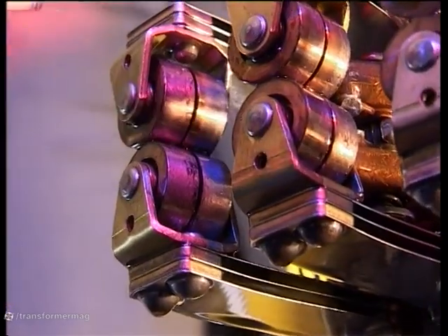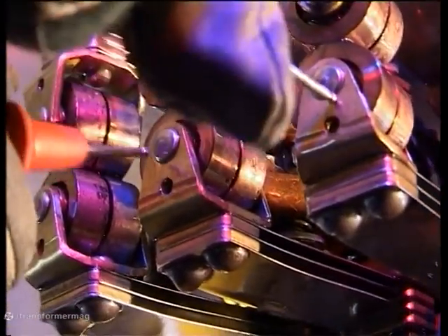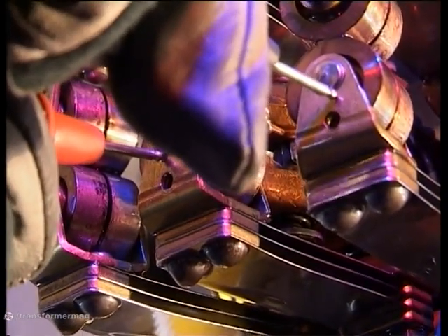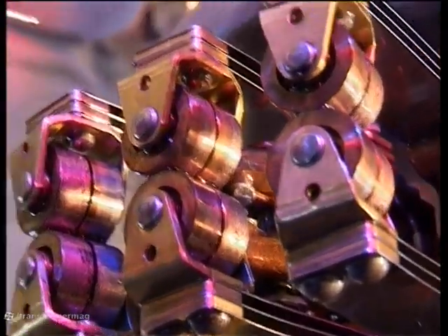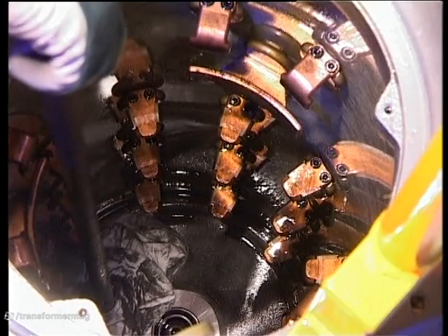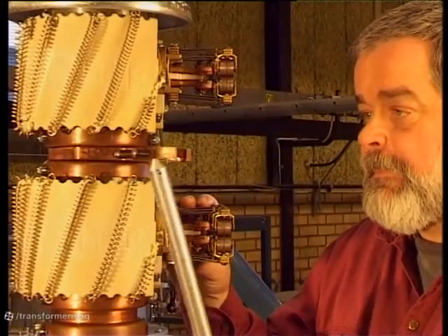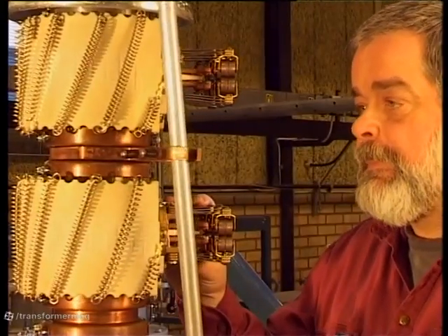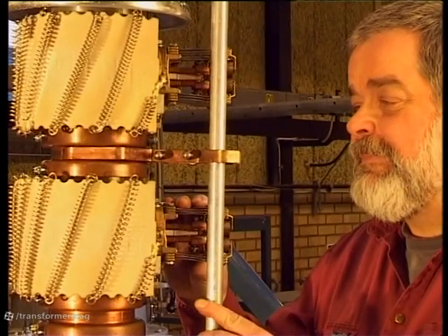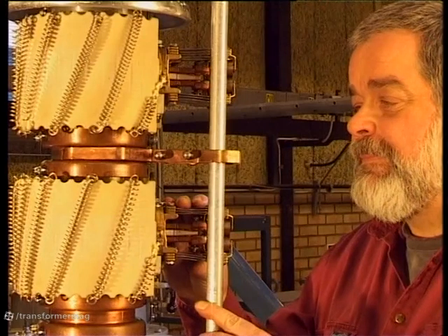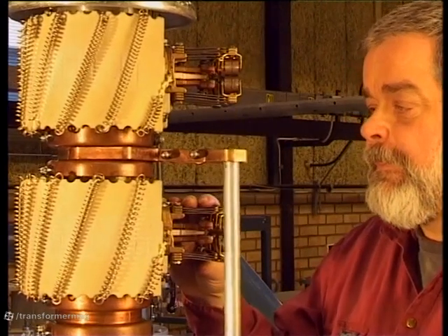Check that screws, bolts, etc. of contacts, resistors, and other parts have not worked loose. Before starting to lower the selector switch, check that there is nothing left behind in the selector switch cylinder. Before lowering, position the moving contacts and the current collectors in the gaps where the fixed contact blades were removed. The moving contacts of the changeover selector must be positioned between two long fixed contacts.